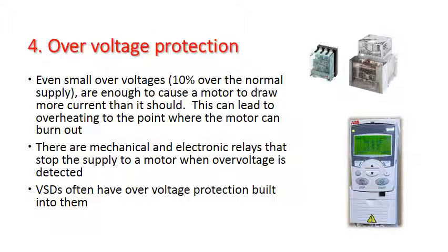The opposite side of that, overvoltage protection. Small overvoltages, it says here, 10% of the normal supply are enough to cause a motor to draw more current than it should, and you're going to end up overheating that motor and burning it out. It's going to cost you money. So you need to protect from overvoltage. There are overvoltage relays once again, and also VSDs can incorporate overvoltage in their software as well.